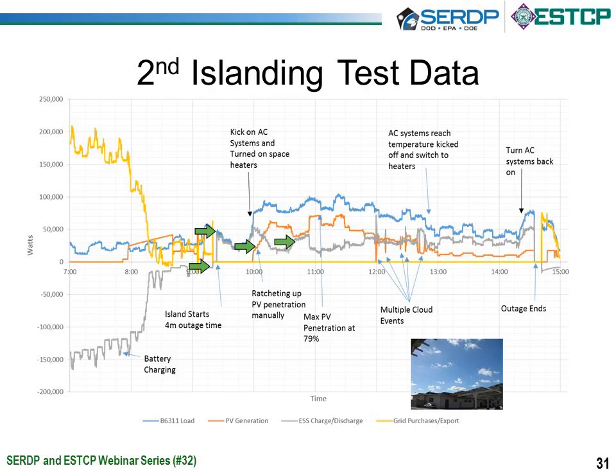And you see the battery system started dropping its power levels to compensate for the fact that the PV system was now providing and sourcing more of the power. As the PV system drops down low, we reduce the amount of PV power. You can see the battery responding and picking back up the remaining load required.